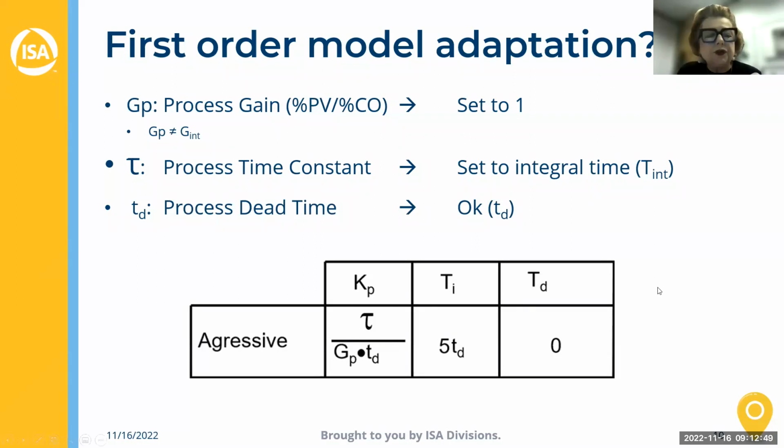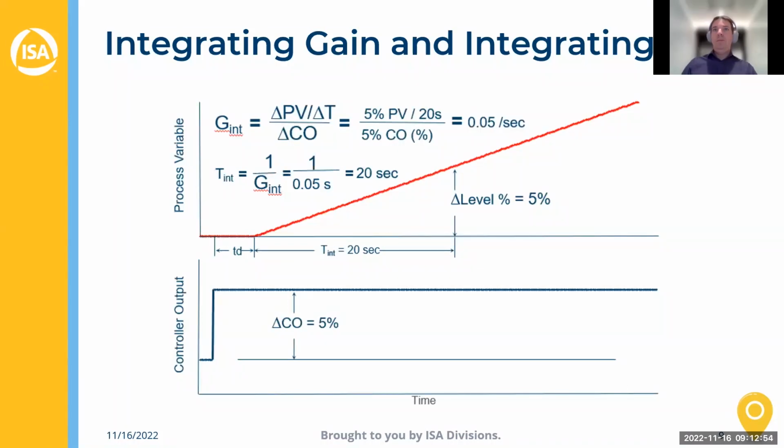So Maxim, Roger Henley had two questions about the ramp. Can we ask him right now? Yeah, no problem. Roger, would you please turn yourself on? I was just asking, in this process, when you're calculating your dead time, I assume you take all of your ramp out of your VFD, so that a change in the CV is an instantaneous change in the pump speed, as opposed to a ramped pump speed change due to a ramping function on the VFD.